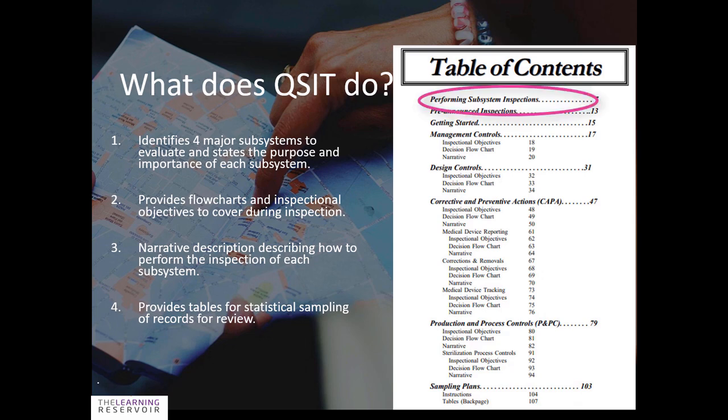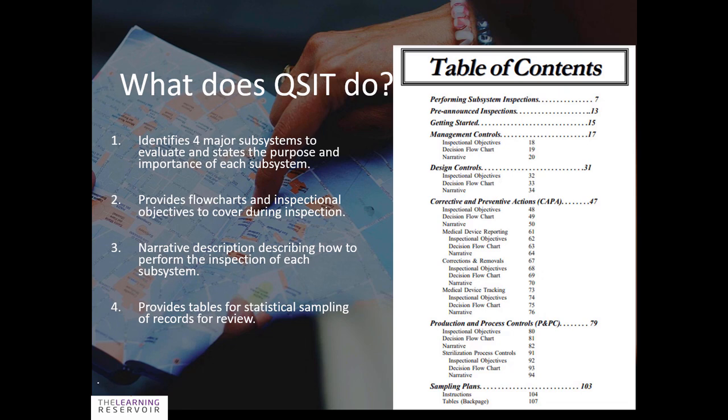It starts off with performing subsystem inspections, a bit of introduction, then it talks about pre-announced inspections, then it gives advice to inspectors on how to get started. Then we have our major subsystems, which are management controls, design controls, corrective and preventative actions, and production and process controls. And at the end it gives some guidance and sampling plans.